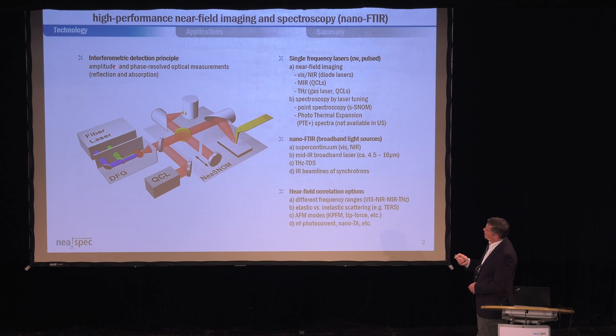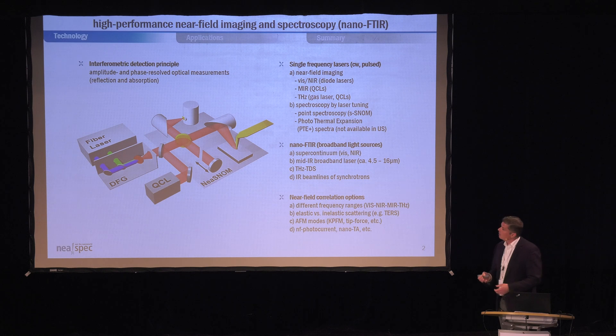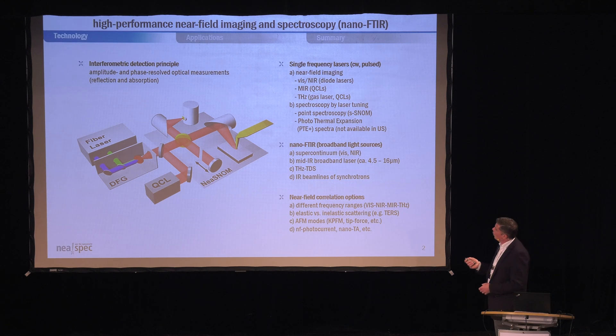The idea is now to show you a few initial results to see what kind of system configuration you can use and what kind of results can actually be obtained. As Sascha pointed out in quite nice detail, we use a system configuration where we illuminate the AFM probing tip with the help of a parabolic mirror. We can use an interferometer or an interferometric detection principle to measure the amplitude and phase of the scattered light, which is related to the reflection and absorption of the measured sample materials. On top of this, you can couple different kinds of sources to this interferometer, and in the last few years we have been quite successful addressing different system configurations.